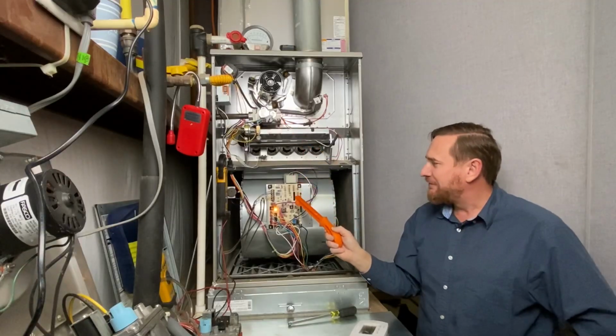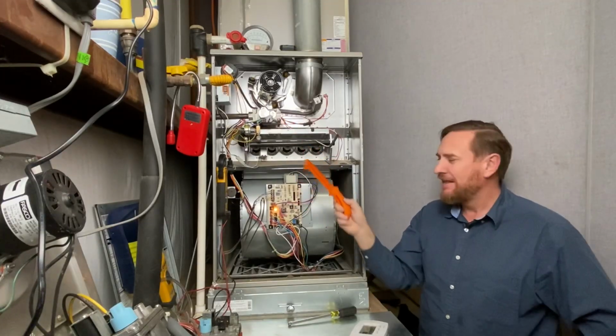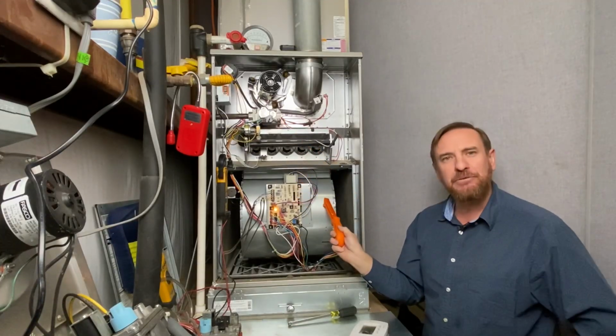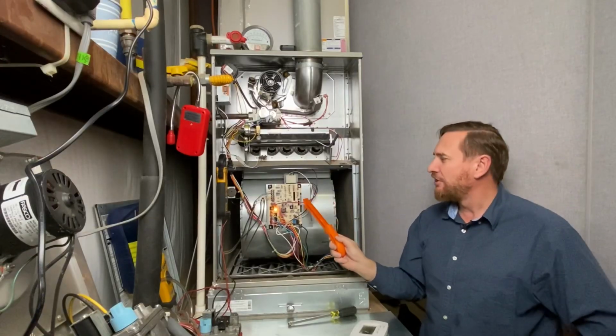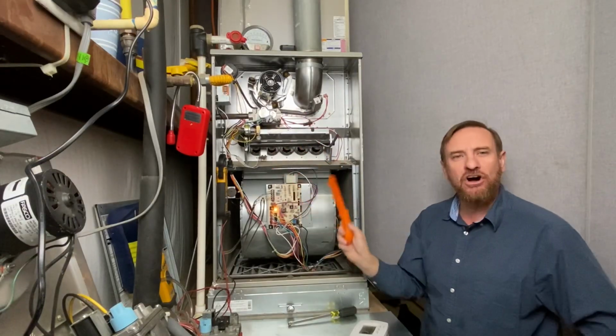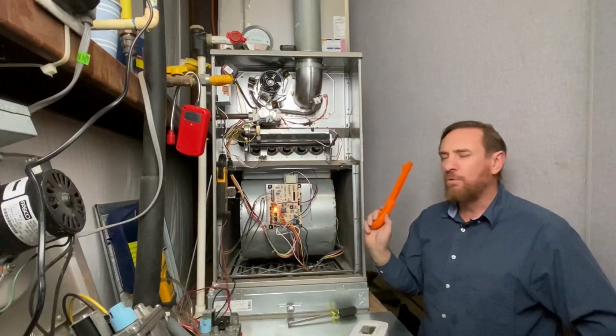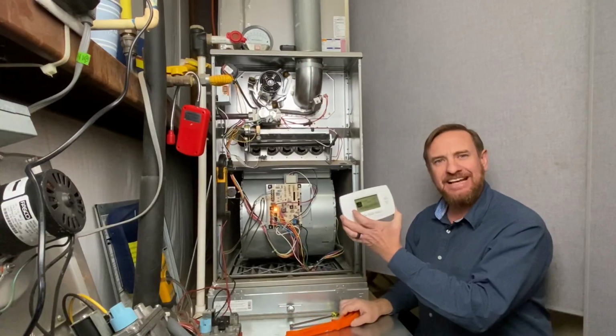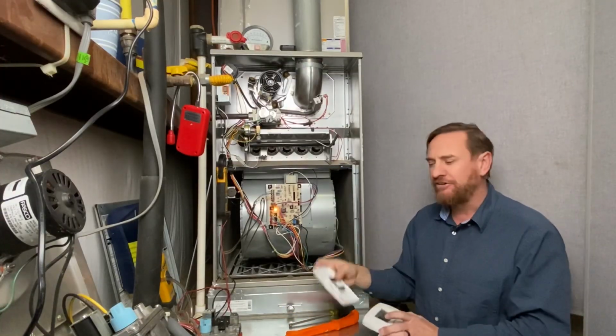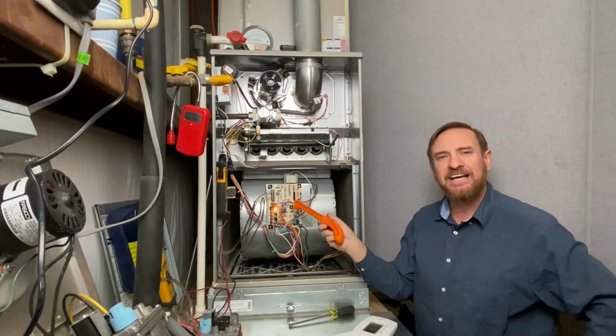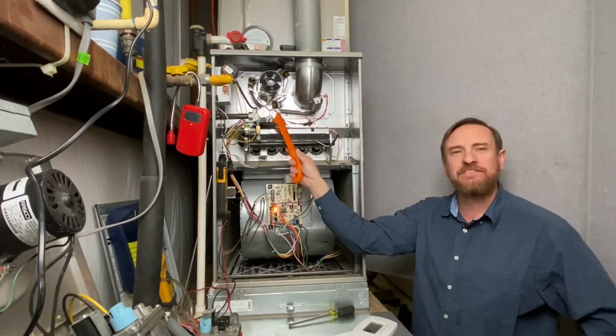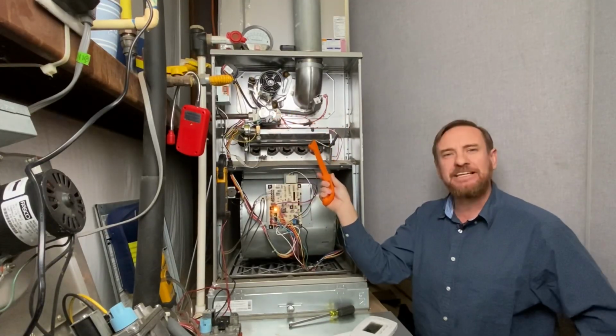The IFC is going to let the heat exchanger heat up. Then the IFC is going to bring on the blower motor, circulating the heat into the house. The whole time, the IFC is going to monitor all the safety components of the system. Once the house heats up, the thermostat satisfies, breaking R and W, killing the signal for heat to the IFC. The IFC immediately shuts off the combination gas valve, which immediately kills the flames.